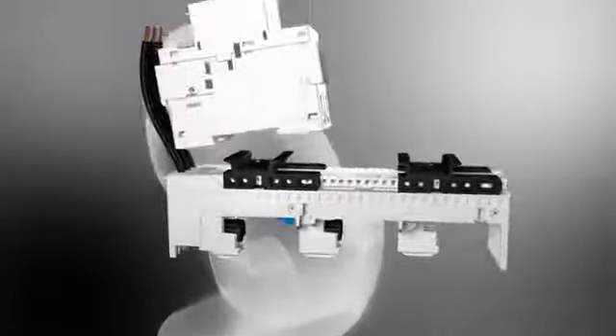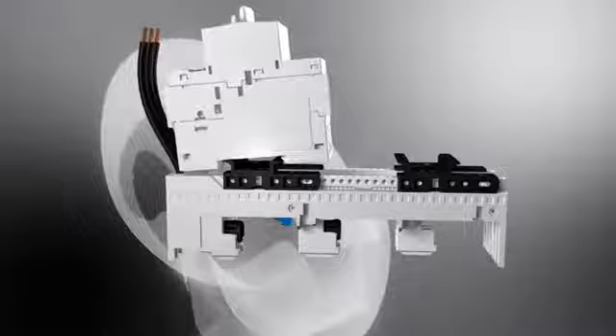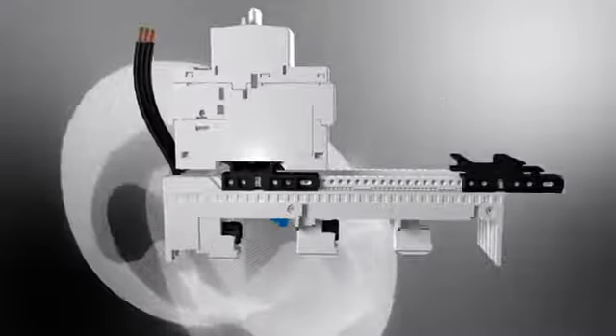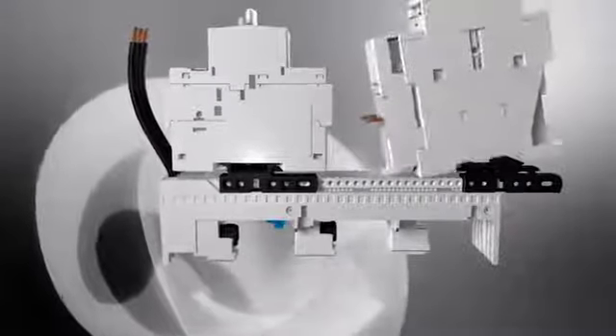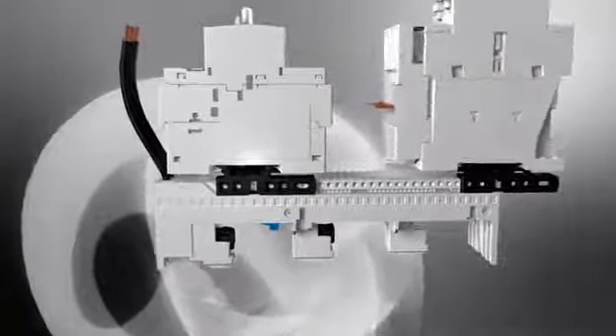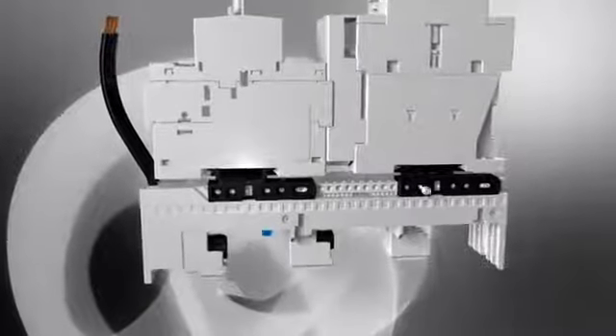Circuit breakers or motor circuit breakers are installed by simply hooking them onto the adapter's upper mounting rail and snapping them into position. After the contactor is placed on the second mounting rail, the rail is screwed to the adapter body in its end position and the motor starter combination wired. Our extensive range of adapters offers various designs for using all customary motor starter combinations on the bus bar.